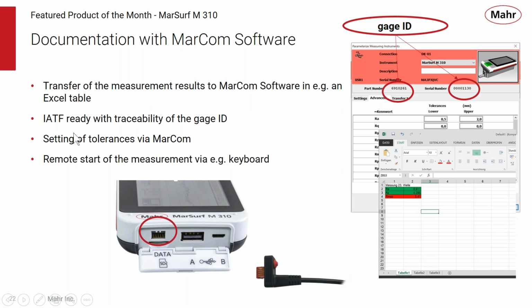And you can also set up the M310 with the free MarCom software by setting the parameters for tolerances and so forth in MarCom, download it to the M310, and the operator has the new values. And you can remotely start the measurement with MarCom via the keyboard or a start key on the unit, or a foot switch. You can do the control remotely.